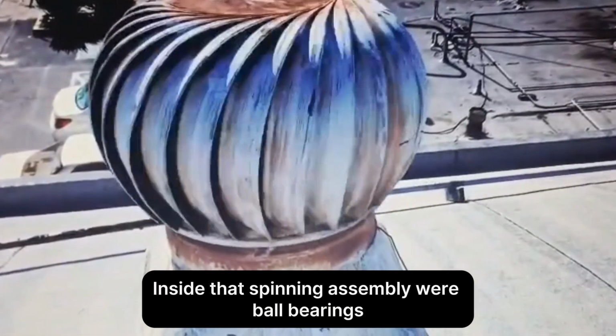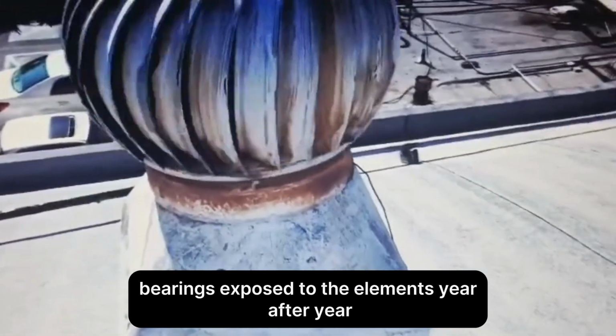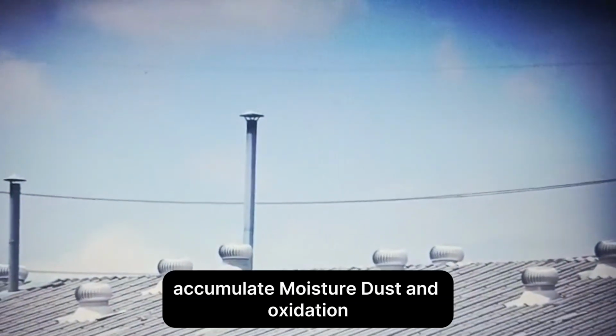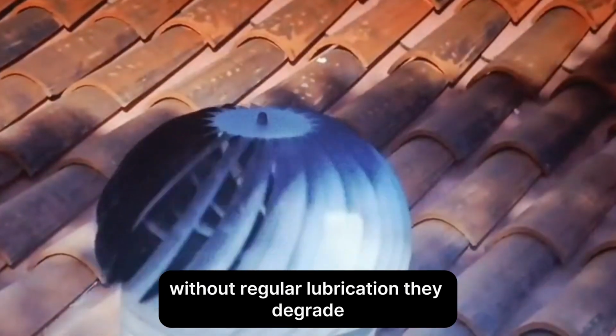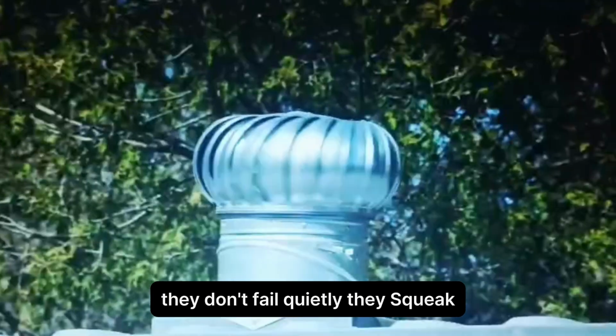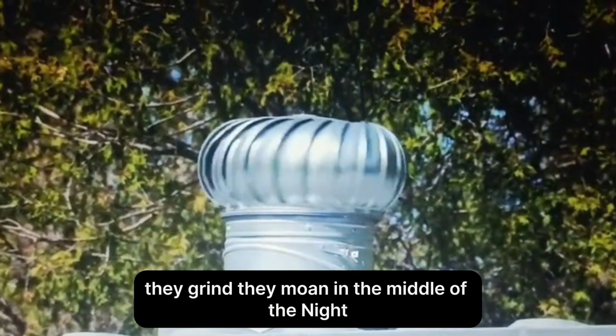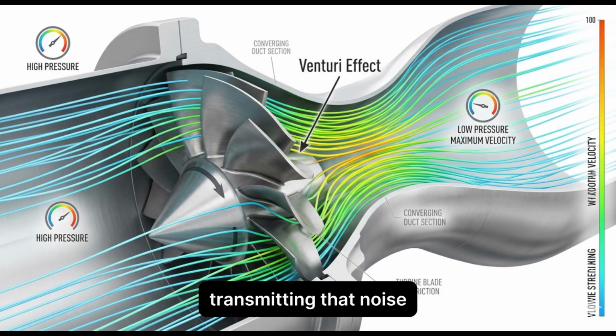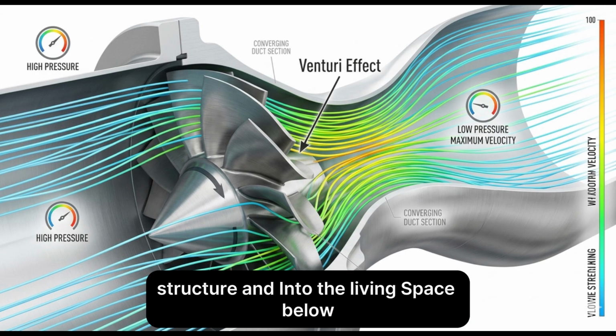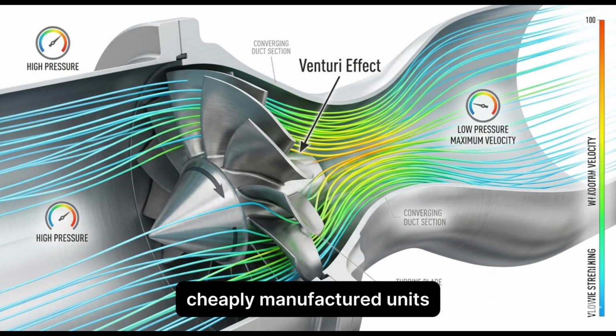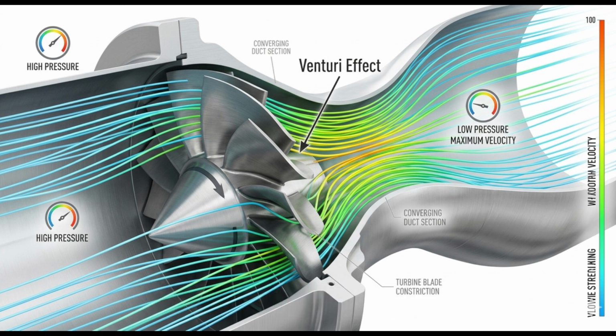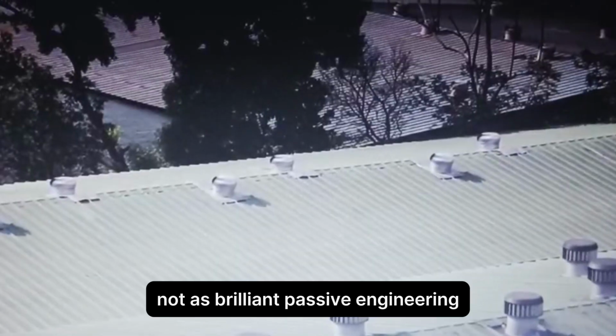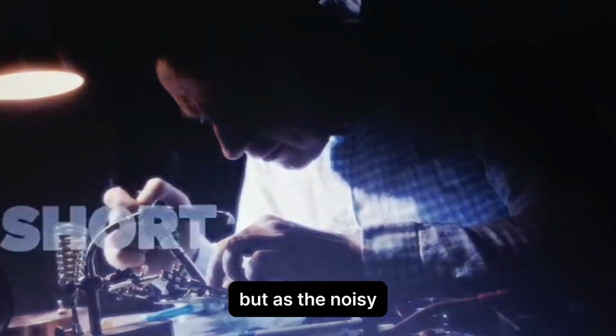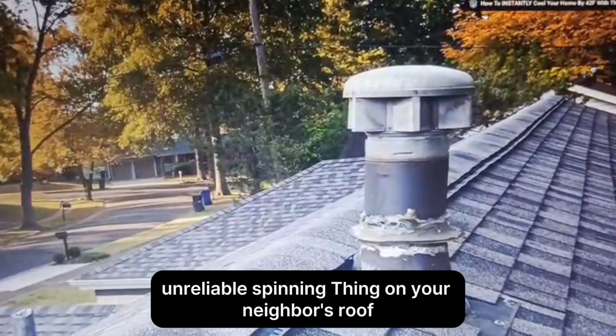Inside that spinning assembly were ball bearings. And ball bearings, exposed to the elements year after year, accumulate moisture, dust, and oxidation. Without regular lubrication, they degrade. And when they degrade, they don't fail quietly. They squeak. They grind. They moan in the middle of the night, transmitting that noise directly through the roof structure and into the living space below. Cheaply manufactured units, and the market was flooded with them, were especially prone to this. And over decades, the turbine ventilator earned a reputation not as brilliant passive engineering, but as the noisy, unreliable spinning thing on your neighbor's roof.